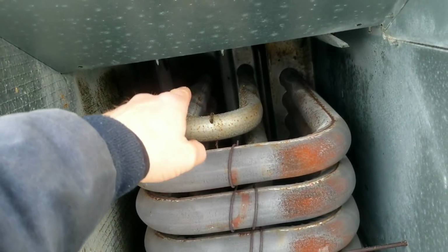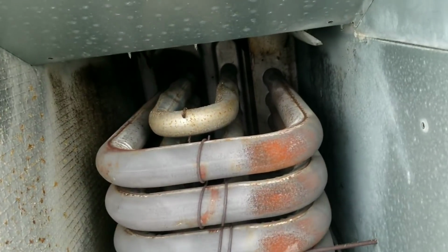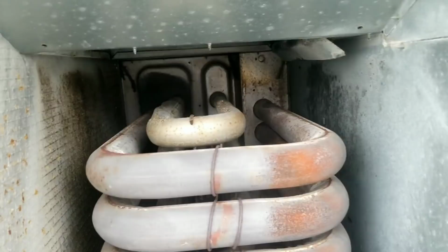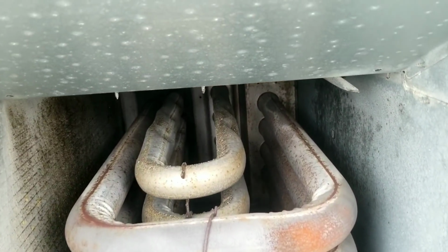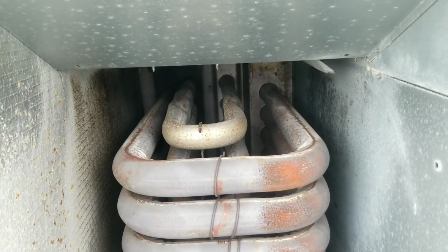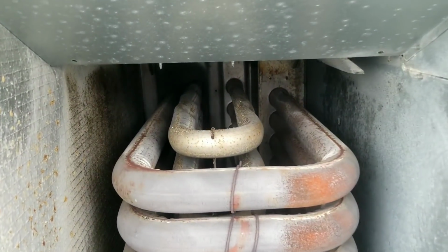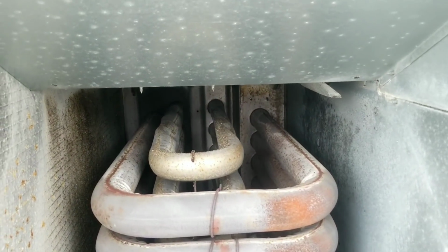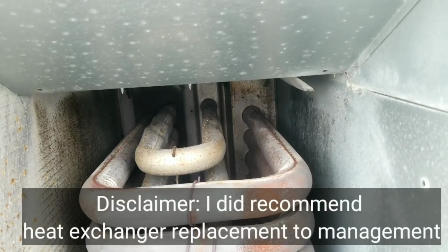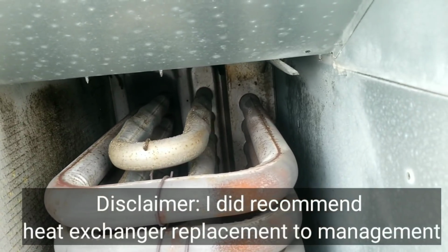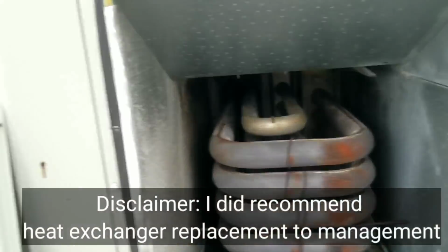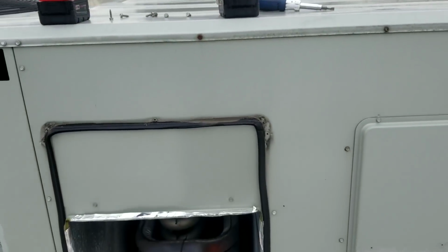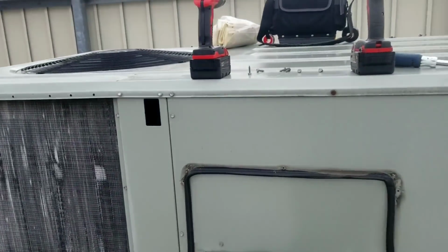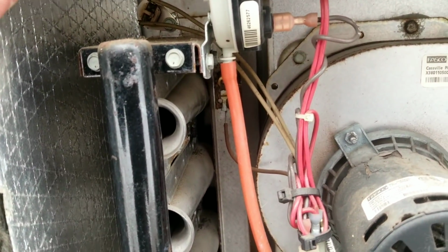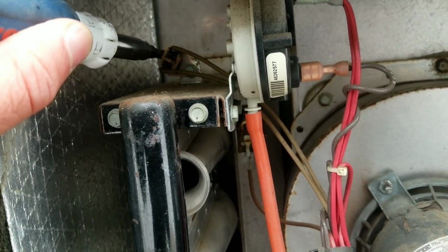My only area of concern is way up front where I can't see, and I can't really disassemble the entire machine to see the front of the heat exchanger. At that point, I might as well just quote to replace it, because you're talking pulling the blower out, the motor, just to get up there into the front. But from what I can see back here, there's no openings or anything like that. So we're gonna reset this, fire it up, and see if I do actually have rollout or if I just have a failed rollout switch. Let's reset our little rollout switch right here very carefully.